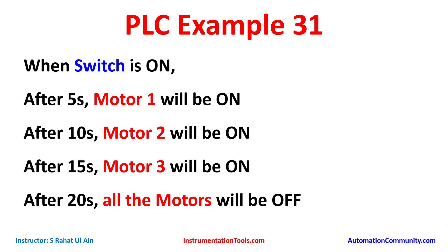When the switch is turned on, it will wait for 5 seconds and after 5 seconds Motor 1 will turn on. It will remain on for 15 seconds, because after turning on the switch, after 20 seconds all the motors should be off. After 10 seconds Motor 2 will be on, and then after 15 seconds Motor 3 will be on. Motor 2 will be on for 10 seconds and Motor 3 will be on for 5 seconds. When the switch is turned on, after 20 seconds all the motors will turn off.